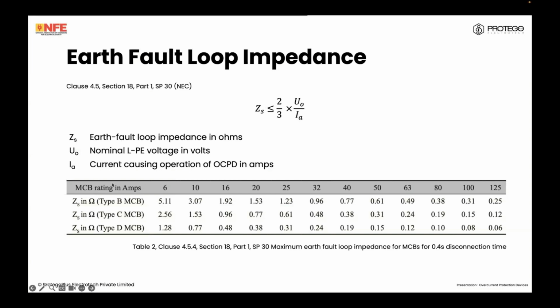Okay. Now, what this means is that for a particular circuit breaker, say 20 amps MCB type B, the maximum earth fault loop impedance measured has to be 1.53. For type C, it becomes half, 0.77. And for type D, it becomes even half of this, 0.38. Remember, this is only for 0.4 second disconnection. If, for example, a D curve MCB is protecting a distribution circuit and you require 0.5 seconds, there's a different time that has to be calculated. This data will again be given to you by the manufacturer.